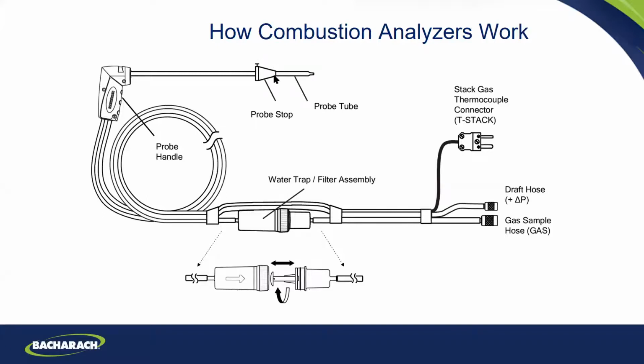You can get our Insight Plus, which comes with a probe stop. It's an accessory for the Intech. Here we have a thermocouple right here, and thermocouples read right at the very tip. So you want to put that in your process at the hottest spot in the stack, which is pretty much the middle. So you're going to be pulling a sample.